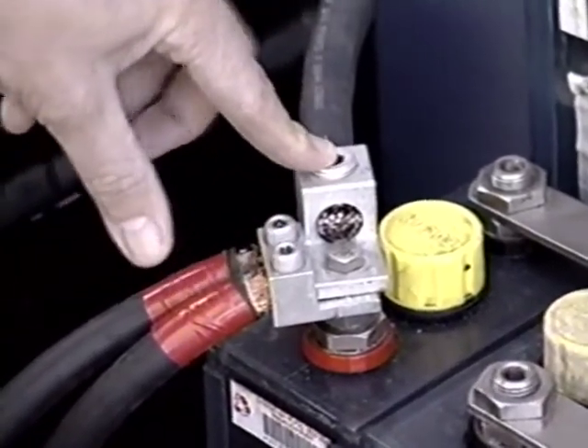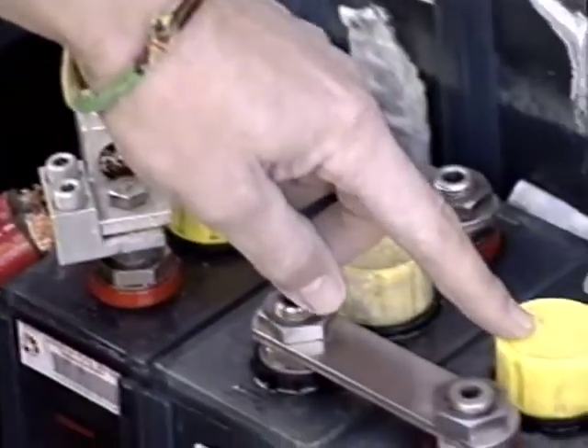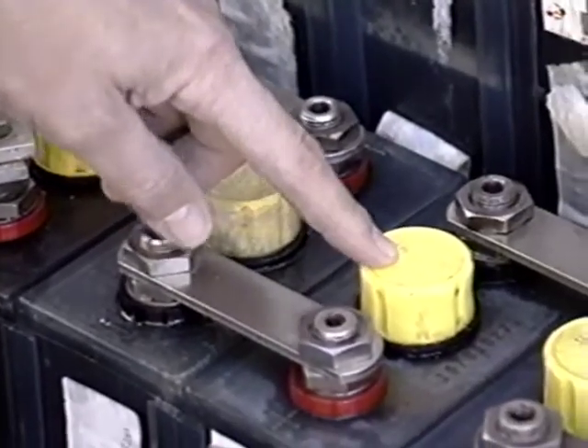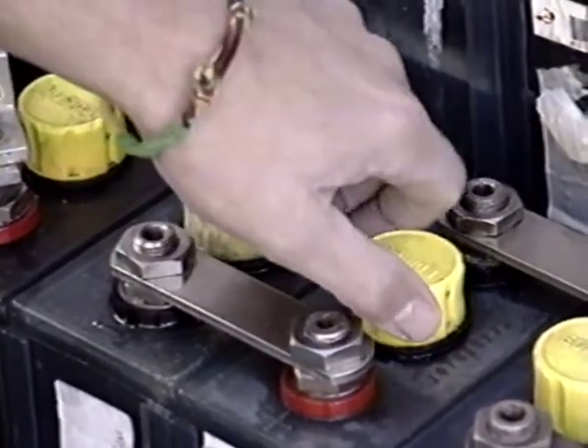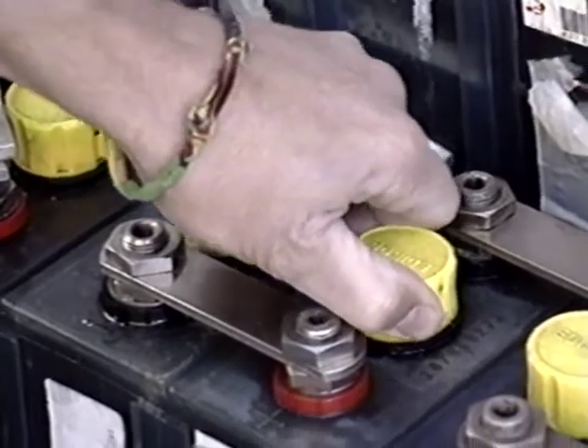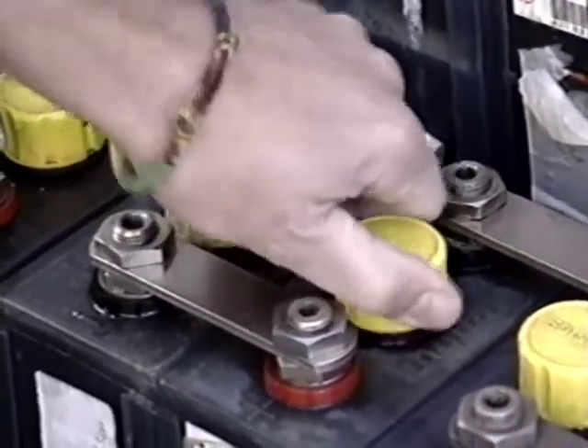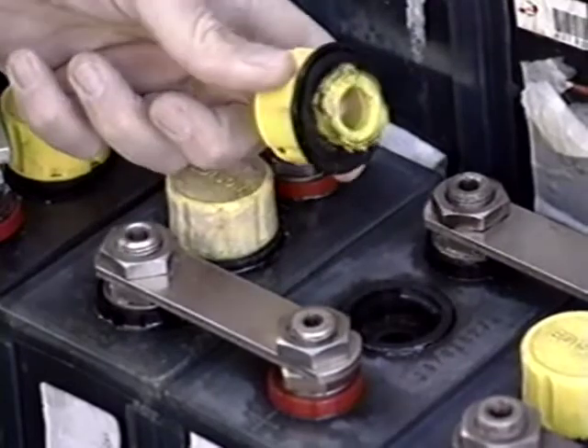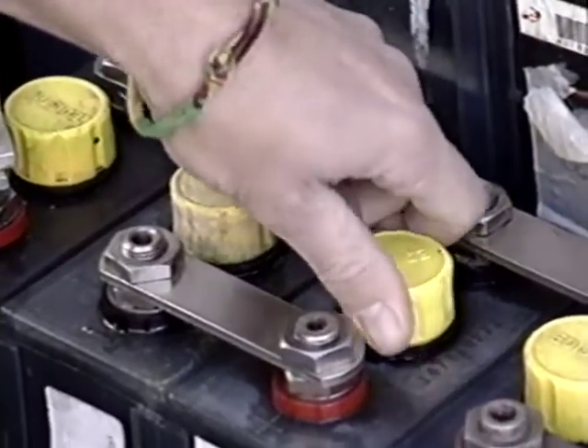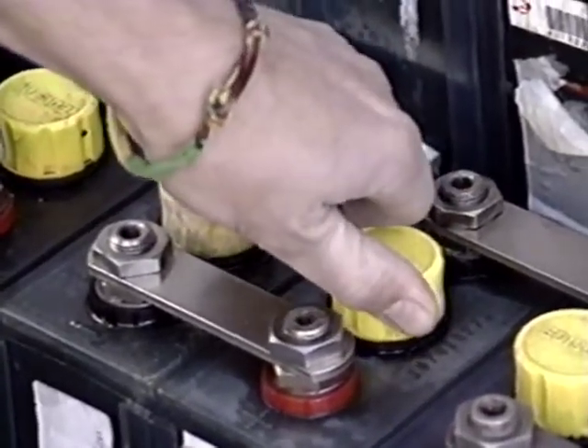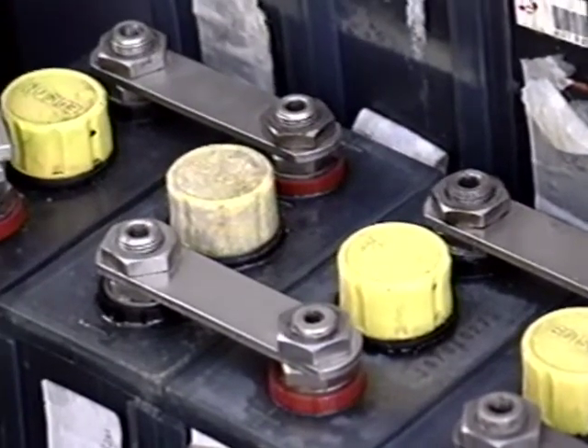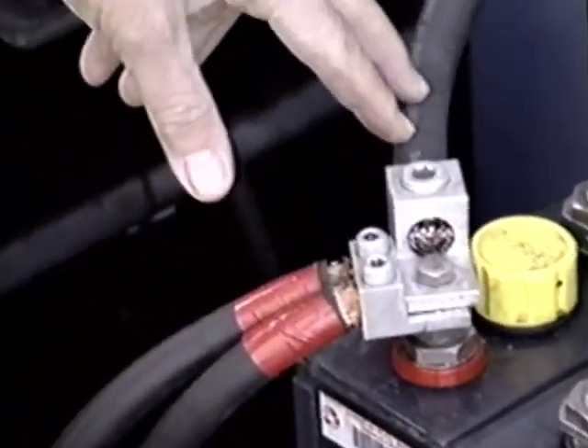The second thing we want to do is to make sure that we have the proper electrolyte level inside the battery, the right amount of water. These are wet batteries and we need to keep them with the right amount of fluid. The third thing we want to do is to keep the battery bank as clean as possible so that we don't have corrosion and therefore loose connections as well. Those three things are really important to do, and the batteries require more maintenance than any other part of a PV system.